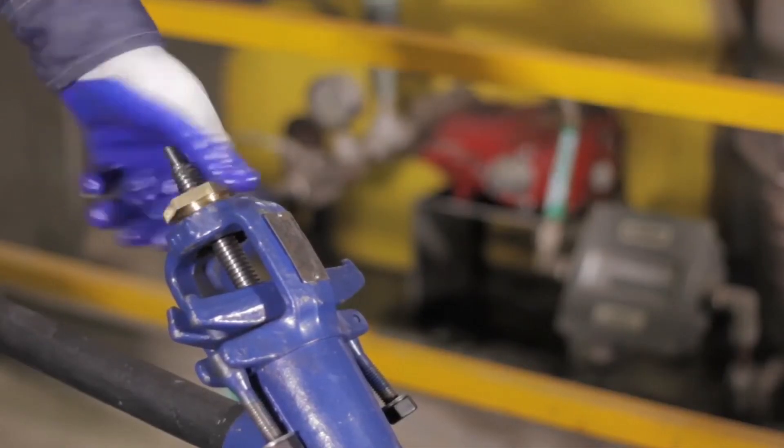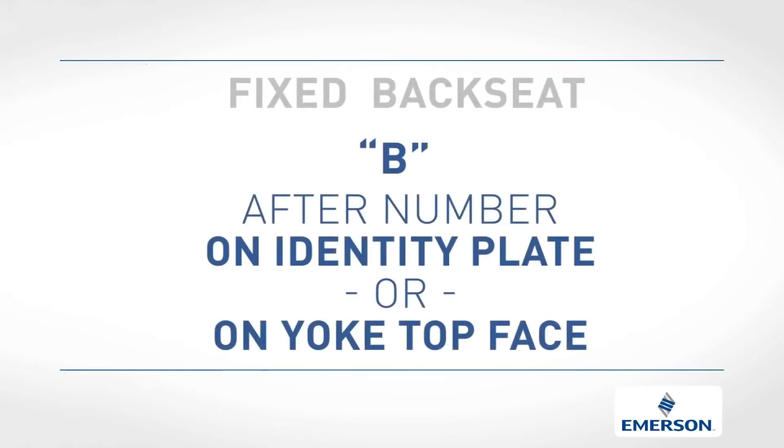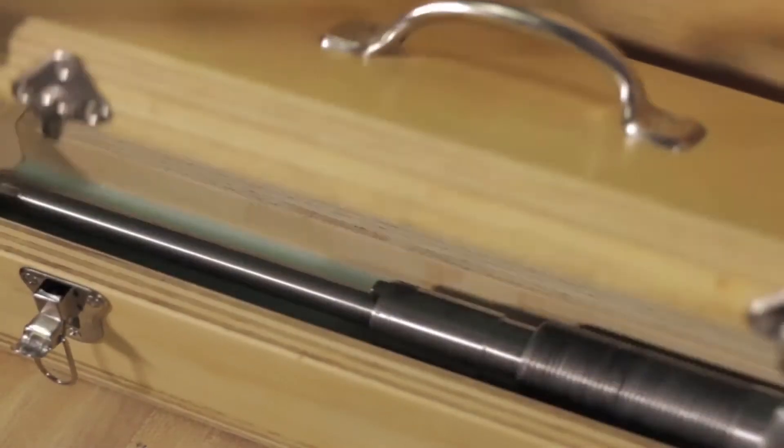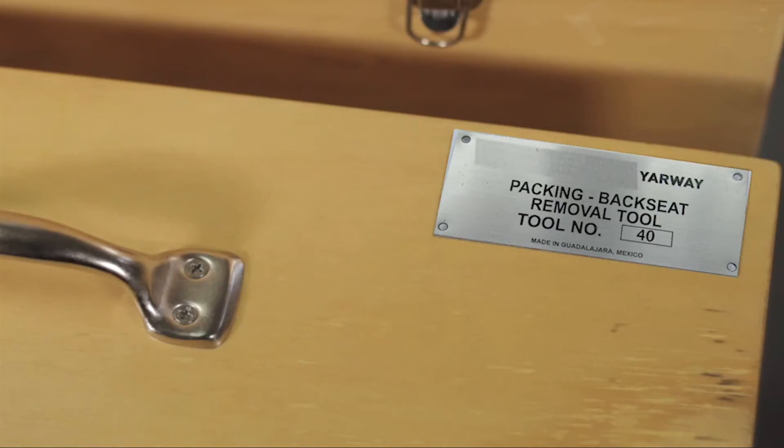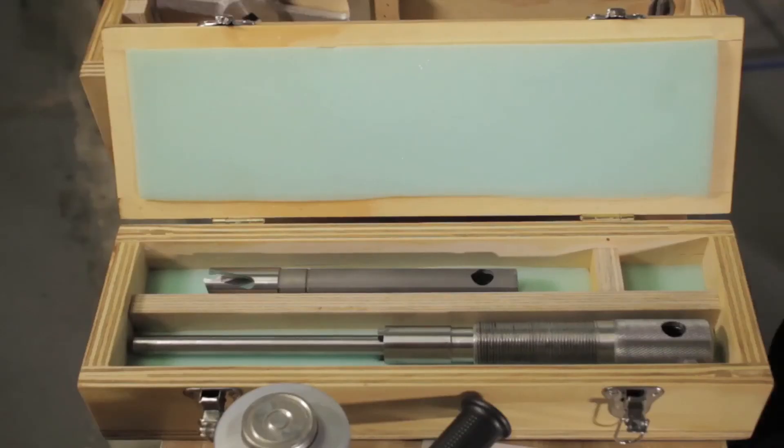Next, you can remove the tack weld so you can unscrew the yoke bushing. A fixed backseat valve is identifiable by a letter B after the number on the valve identity plate, or by a B stamped on the yoke top face. A special tool is used to remove the packing and get to the valve's permanent backseat.